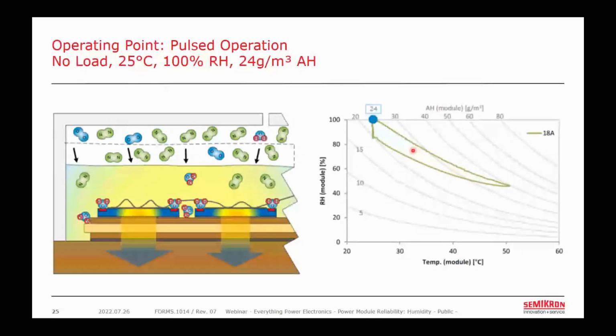The absolute humidity that we've returned to is now 24 grams per cubic meter, which is higher than that starting 20 grams per cubic meter that we registered earlier, which means that our relative humidity is also higher than before. And you can see we started here, we went down here, and when we return, our relative humidity has sort of overshot, and instead of returning to 85, it actually reaches close to 100% relative humidity. And at 100% relative humidity, we know from earlier diagrams that the dew point is the air temperature. And if there's anything just slightly cooler than the air, there's a risk of condensation.